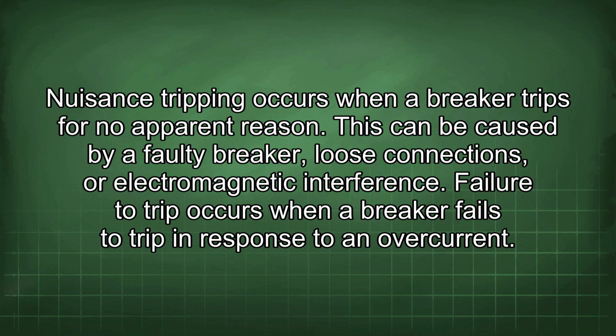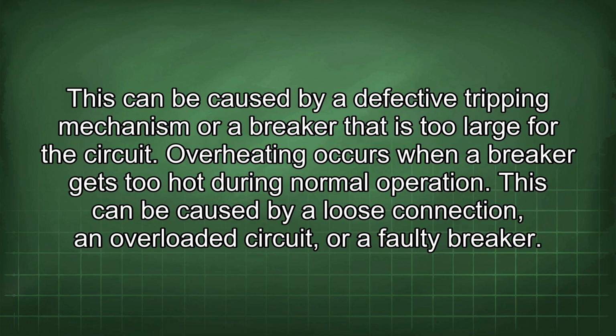Failure to trip occurs when a breaker fails to trip in response to an overcurrent. This can be caused by a defective tripping mechanism or a breaker that is too large for the circuit. Overheating occurs when a breaker gets too hot during normal operation. This can be caused by a loose connection, an overloaded circuit, or a faulty breaker.